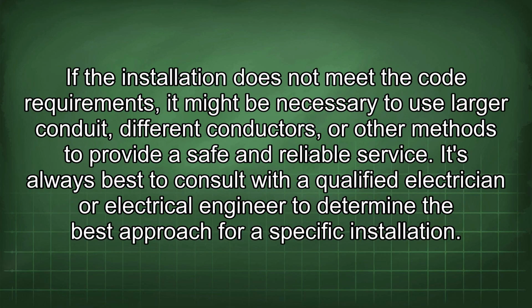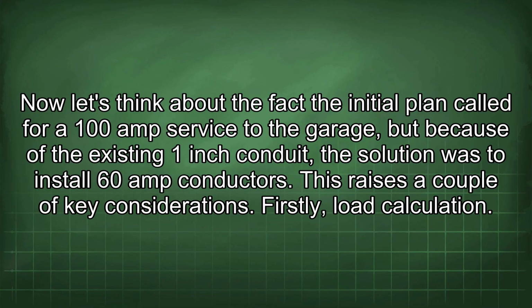If the installation does not meet the code requirements, it might be necessary to use larger conduit, different conductors, or other methods to provide a safe and reliable service. It's always best to consult with a qualified electrician or electrical engineer to determine the best approach for a specific installation. Now let's think about the fact the initial plan called for a 100 amp service to the garage, but because of the existing 1-inch conduit, the solution was to install 60 amp conductors. This raises a couple of key considerations.